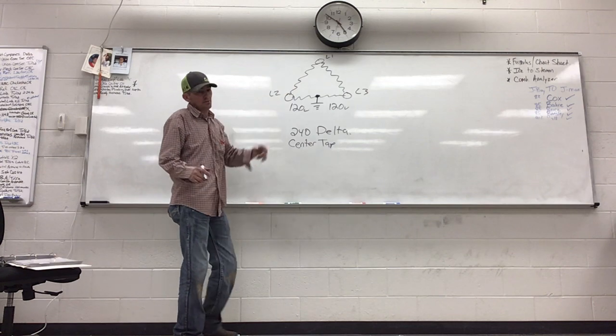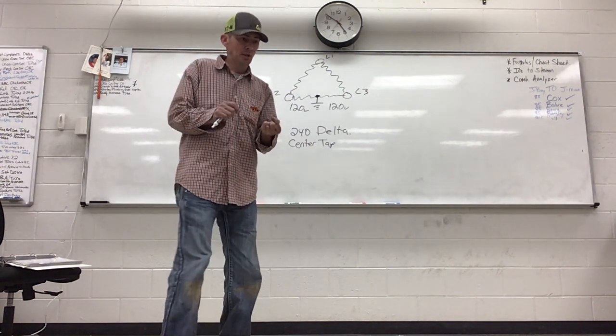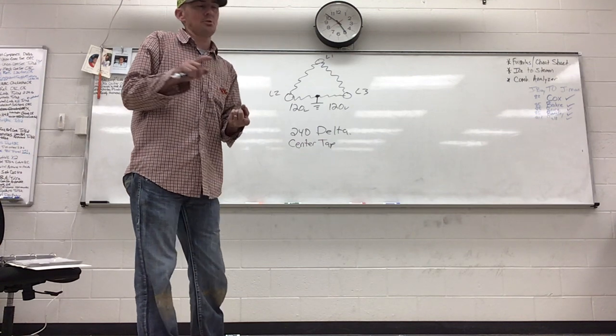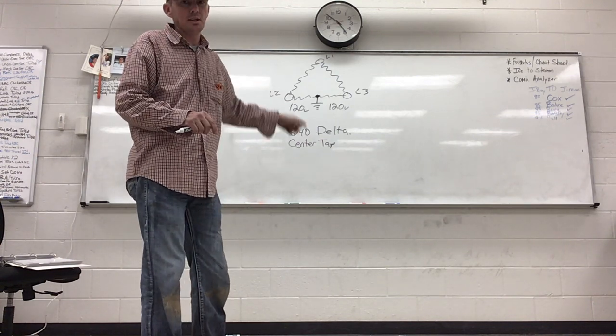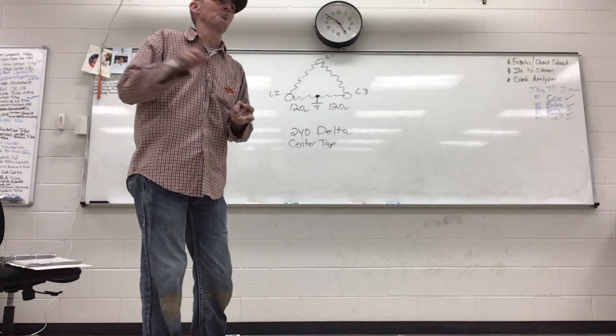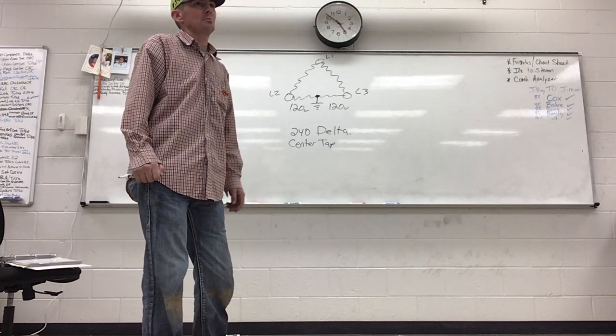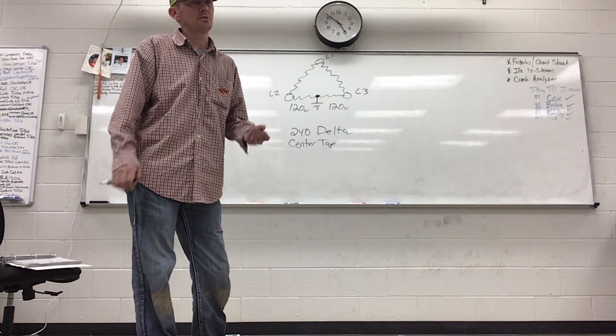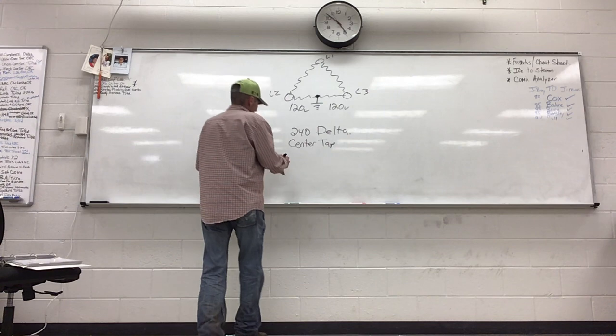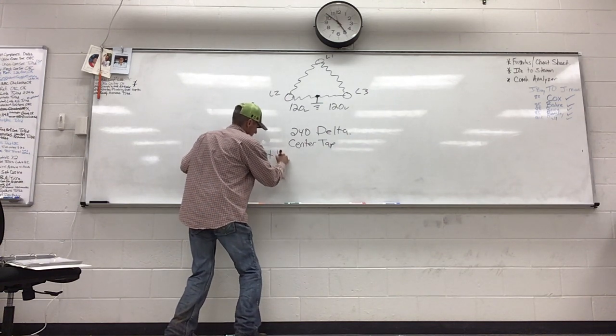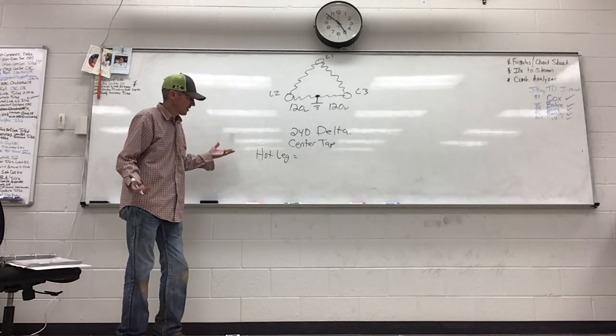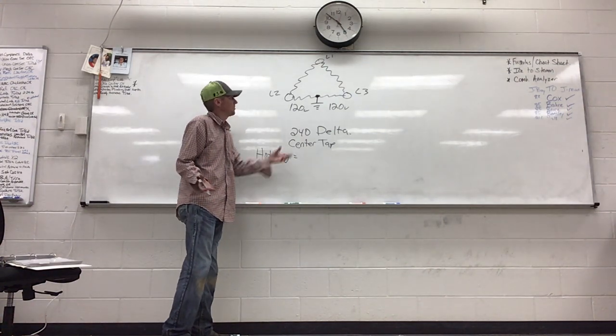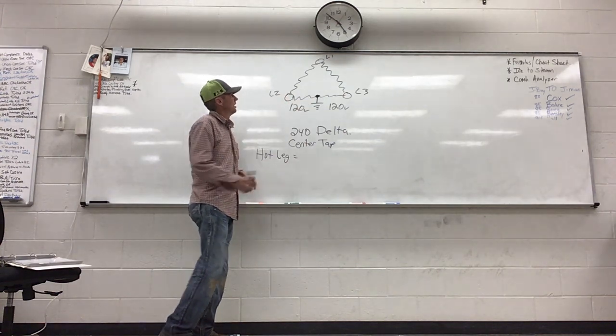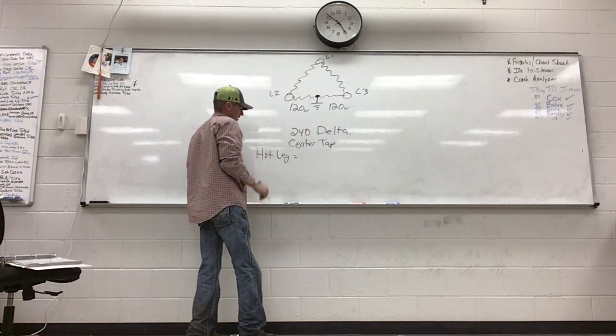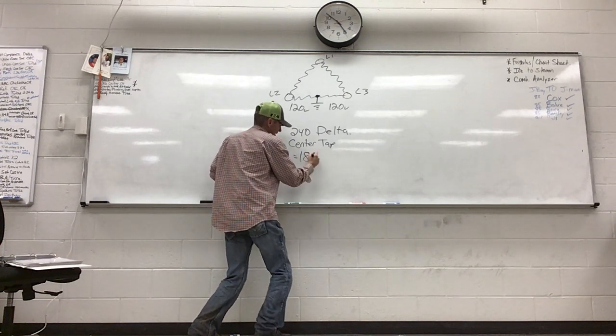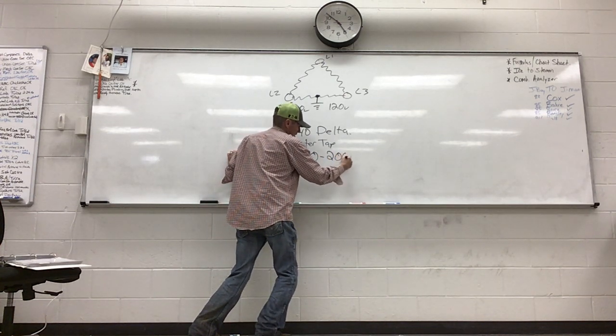And guys, that's called, you've probably heard this before, the center tap transformer. But that hot leg is called the Widowmaker. Stinger leg, yeah, all that, okay, but I'm just going to call it the hot leg. On that hot leg you're going to get something higher than 120, because look at how much is being induced onto it. It's getting all this, so on that hot leg you're going to get at least 180 volts, I'll just put something like 180 to 200 volts.